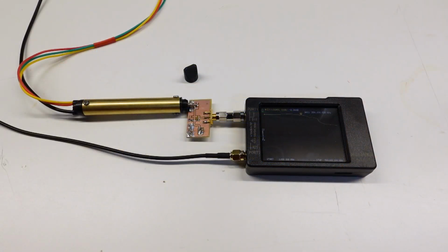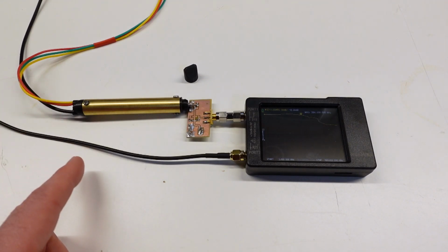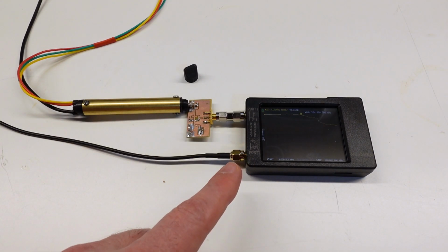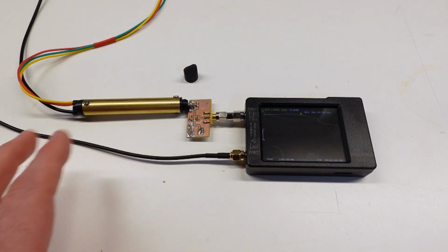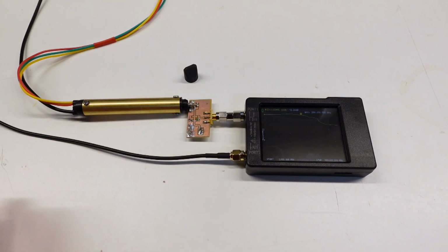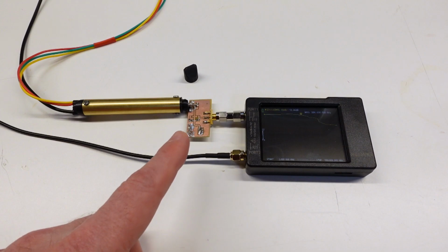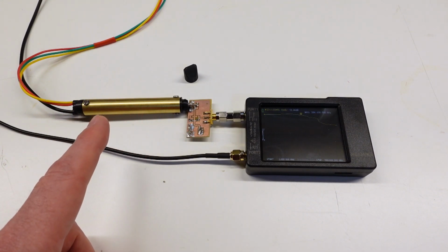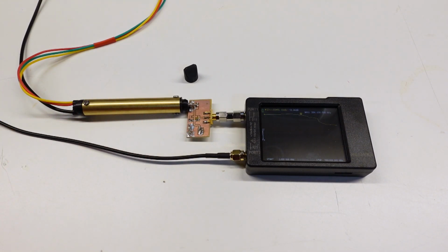I can also use my Nano VNA to measure probe performance by connecting the probe output signal to port 2 and looking at the S21 parameter. This is feasible for a couple of reasons. First, the nano's output signal on port 1 is within the sense range of all 3 probes.